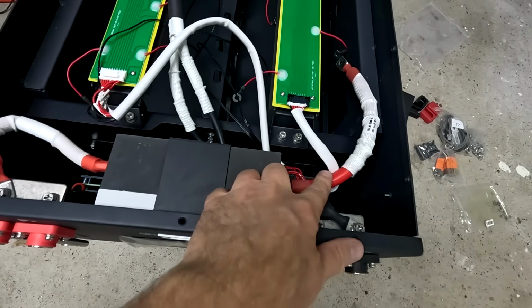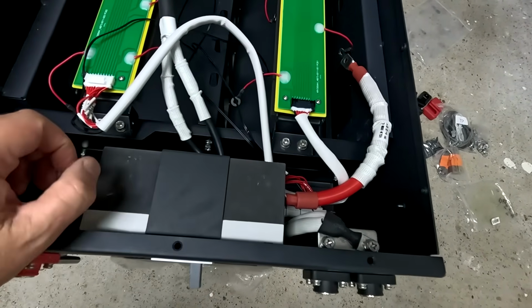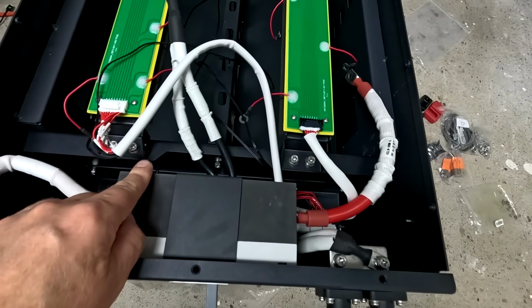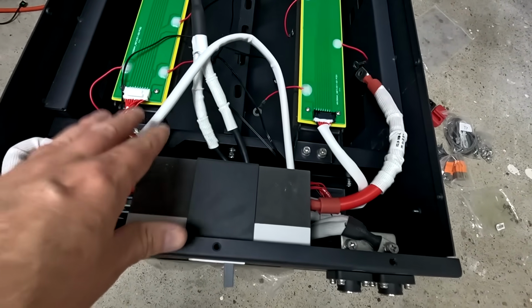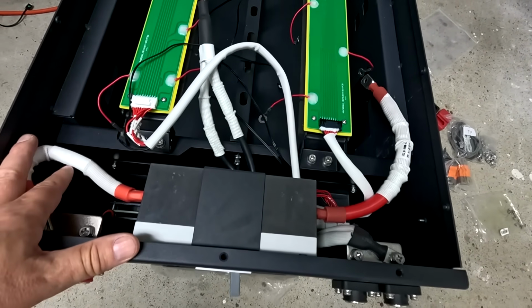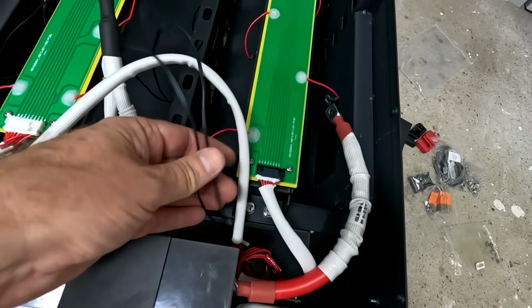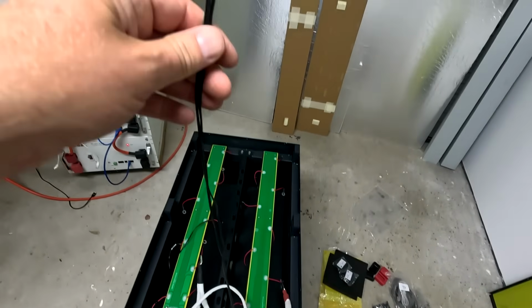And we've got 35 square millimeter cable. I would really like to see a Class T fuse here with a breaking capacity of 20 or even more kiloamps. I'm not a fan at all of this solution here with these temperature sensors.